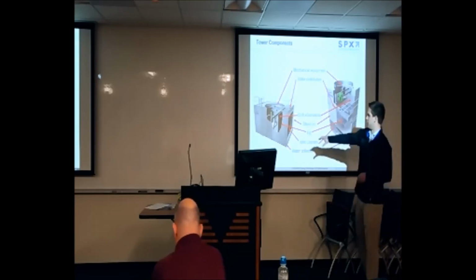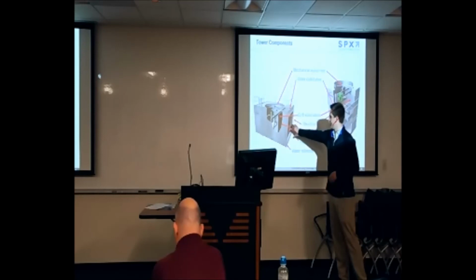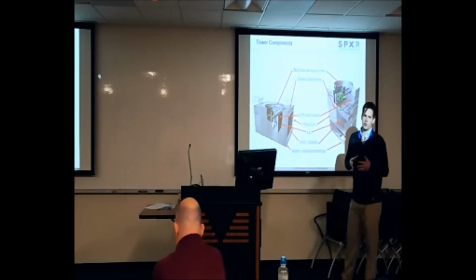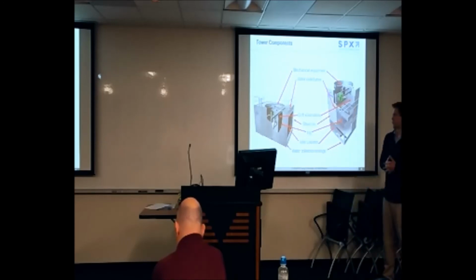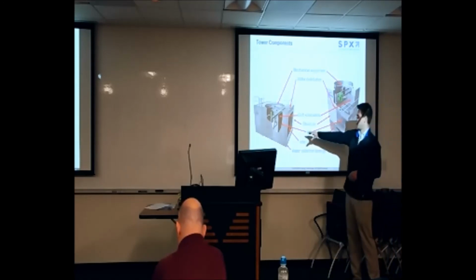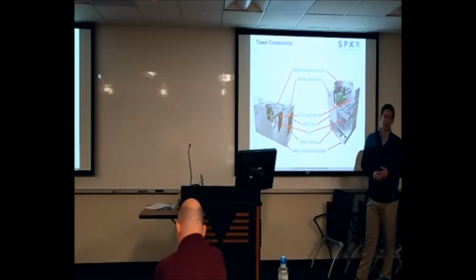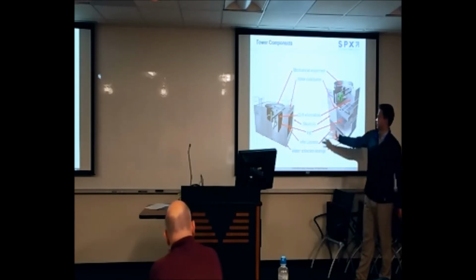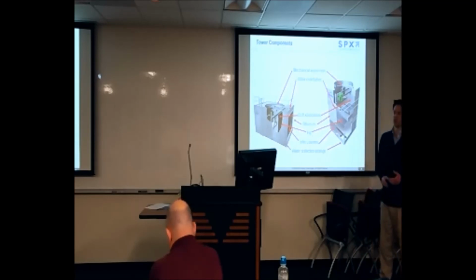The fill here, which is this black PVC mesh-looking material, this is really where your thermal transfer is happening. So a lot of people will consider the fill probably the most important component within the cooling tower. Your fill is where your water comes into contact with your air, cooling the water for the purpose of the system. Now, what you'll find is when you talk about maintenance with fill, it's mostly going to be cleaning and just observing the condition of the fill. Cooling towers are known to be air scrubbers. You basically have a lot of air coming in contact with water. And in Los Angeles, we all know that the air isn't so clean out here. So these cooling towers, if they're not properly maintained, can get pretty dirty. So it's good to observe your fill every once in a while and see if it needs to be brushed or cleaned.